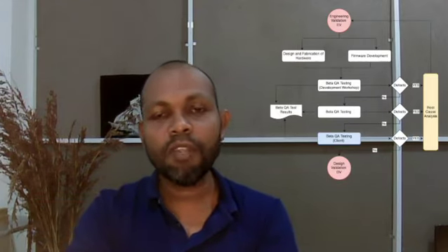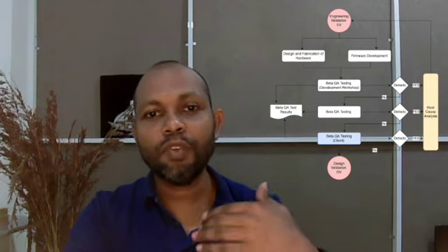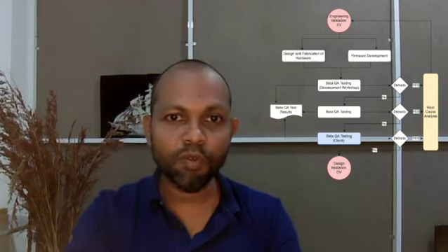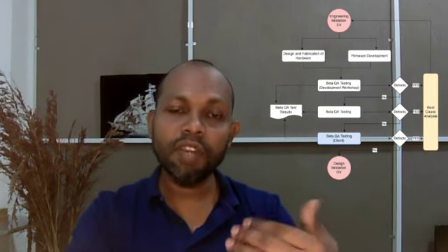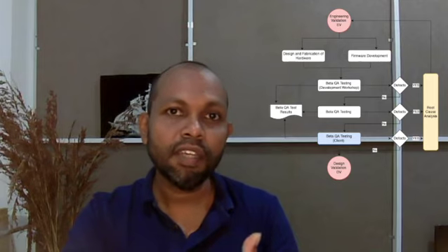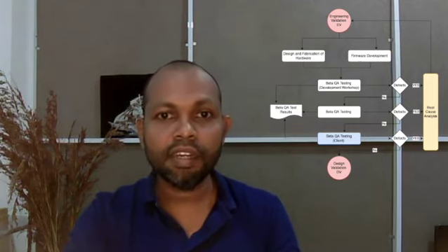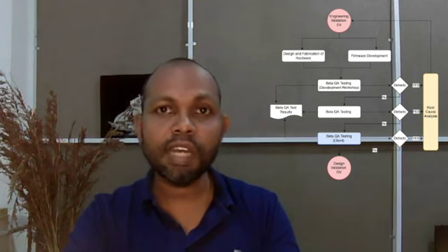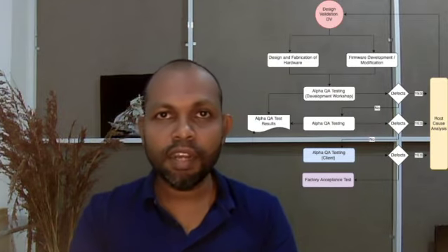Normally in our company, we go through the engineering validation phase. If it passes certain criteria, we go for design validation, or we might have to do a new iteration of EV. And even in design validation, we do a few iterations, maybe 1 or 2, to make sure that we pass all these criteria. Then we can go for factory acceptance testing, and then do the certification and clinical trials with these successful DV samples, and then we can go for bulk design and bulk manufacturing. So this is a very standardized process.